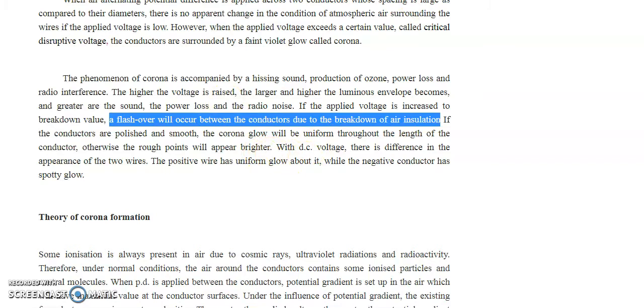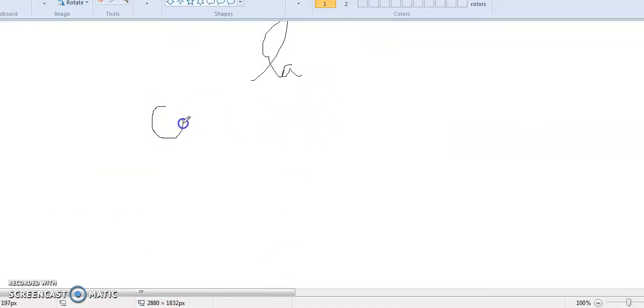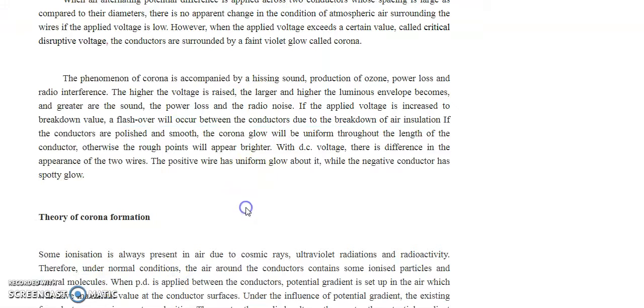That means, you can understand here, if your conductor is circular in nature, you will get a very bright glow around it. Suppose your conductors are made up of many subconductors, that means the surface of the conductor may not be very uniform. You can imagine this type of conductor. In this case you will notice the sparks of the corona. Around these conductors you can see the sparks, and that is another phenomenon you need to keep in mind, right? The corona glow will be uniform throughout the length of the conductor, otherwise the rough points will appear brighter.